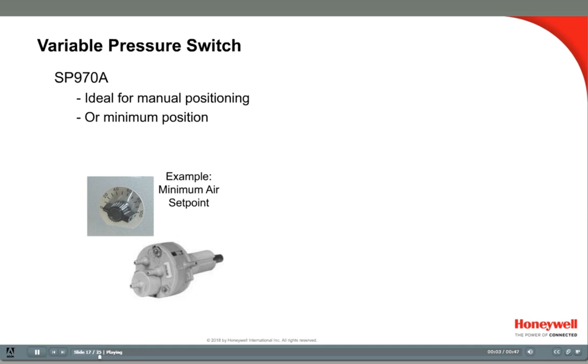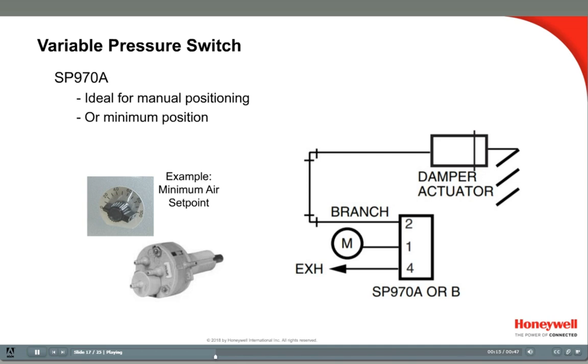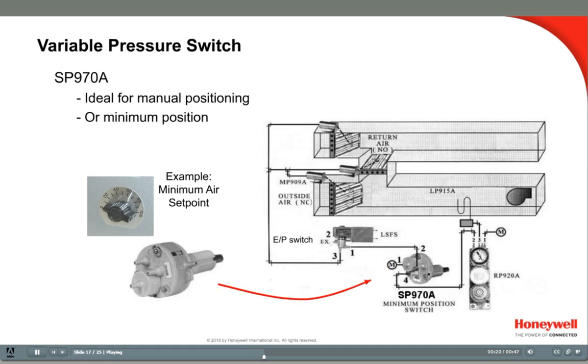The SP970A sends a certain pressure to a damper actuator to hold a minimum position. When the signal from the controller rises above that pressure, it will pass the pressure on to the damper. It is piped to the controller on port 4, to main air supply on port 1, and to the damper on port 2. The SP970A will hold the damper at a minimum position as set on the switch. As the controller's branch signal rises above this setting, the switch will pass the controller's branch pressure to the damper so the damper will open and modulate normally. When the controller's branch signal falls below that setting, it will go back to keeping the damper at a minimum position for fresh air.